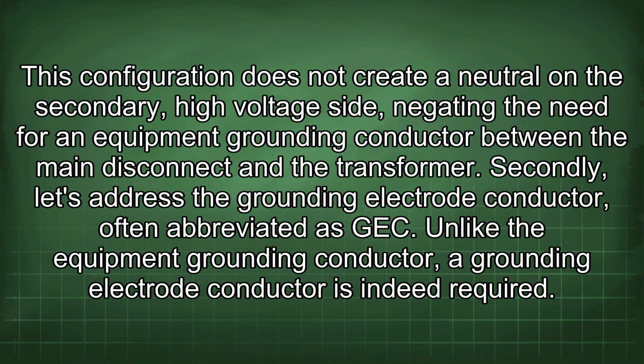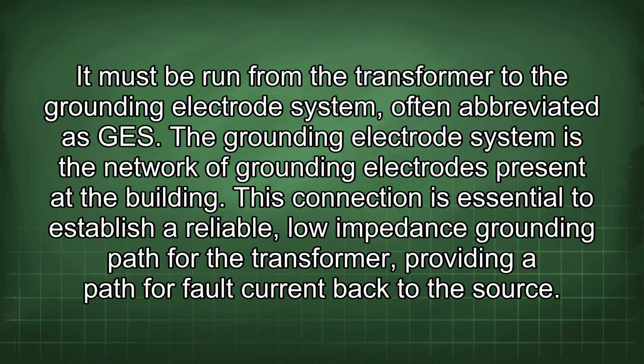Secondly, let's address the grounding electrode conductor, often abbreviated as GEC. Unlike the equipment grounding conductor, a grounding electrode conductor is indeed required. It must be run from the transformer to the grounding electrode system, often abbreviated as GES. The grounding electrode system is the network of grounding electrodes present at the building.